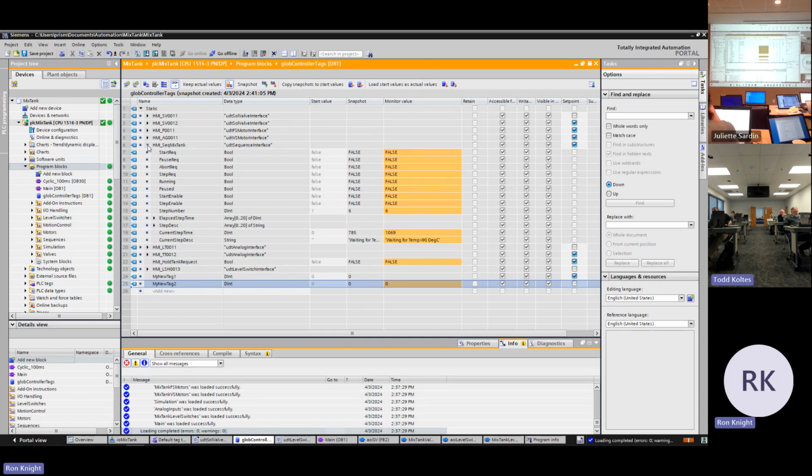So the only way that I would know that you could do that, remember these snapshot values are stored offline with your project, and the HMI doesn't have access to your offline project. But what you could do though, instead of relying on snapshot, is once you have everything tweaked, you then have another global data block in here that you're calling your golden values or whatever it is.